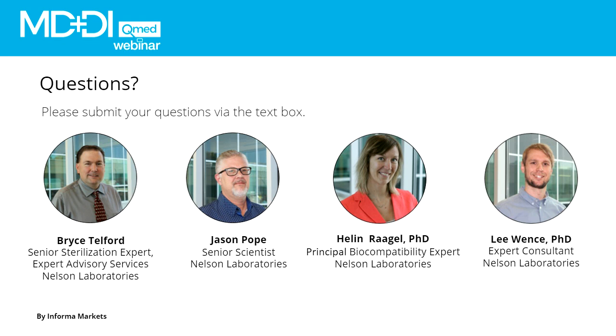Now, when you have too many changes happening at the same time, you might be introducing too many unknowns or variables into the system, and then we might be effectively causing it to become essentially a new device, and I'm making air quotes for the new device, right? So really, when we're doing an assessment to assess the impact of vaporized hydrogen peroxide, just do that assessment one at a time.